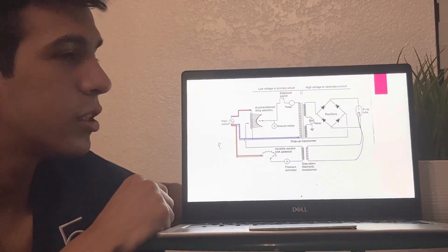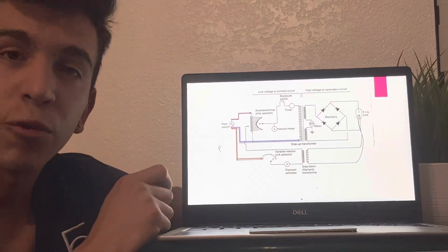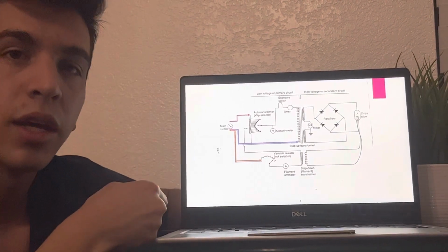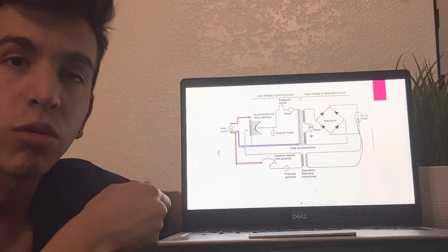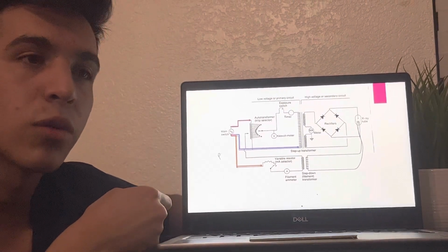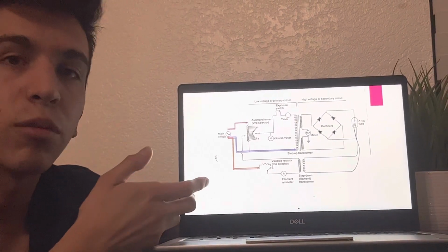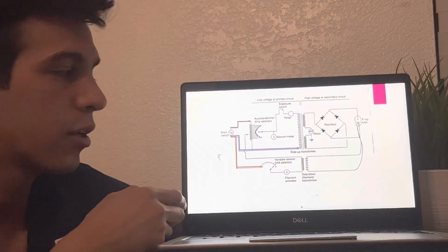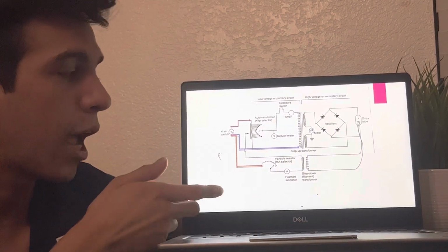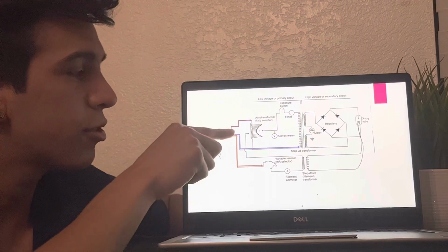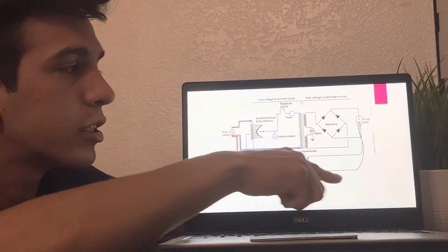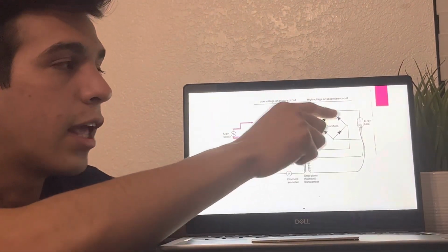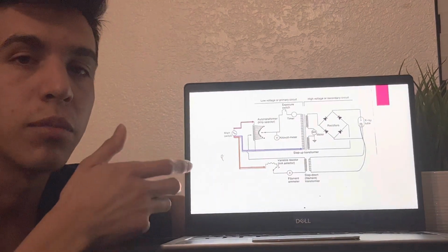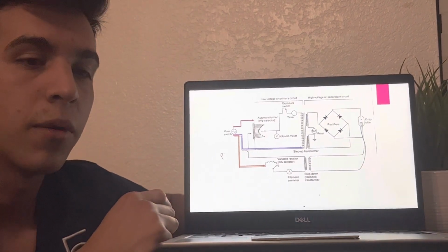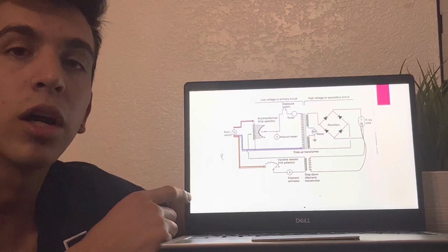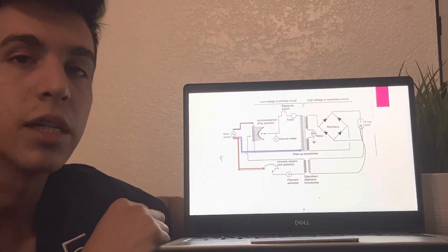So what happens is you're going to grab your patient, but before you do that, you're going to plug in the machine. And what this is doing is the warm-up procedure. Basically, the warm-up procedure is getting the machine from room temperature to operating temperature. During this, these three currents are going to be racing over simultaneously to the filament and the X-ray tube's anode to warm it up to operating temperature. This makes it so that there's no cracking or breaking of any of the components inside of the machine.